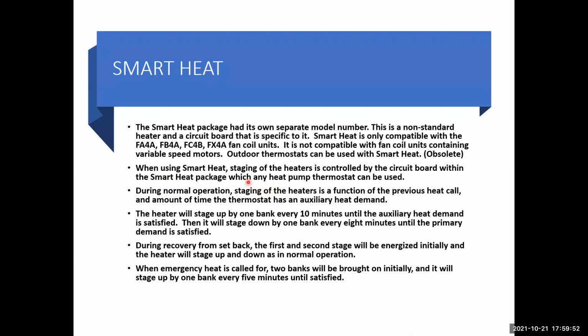When using the smart heaters, staging of the heaters is controlled by the circuit board within the smart heater package, with which any heat pump thermostat can be used. During normal operation, staging of the heater is a function of the previous heat call and the amount of time the thermostat has an auxiliary heat demand. The heater will stage up one bank every 10 minutes until the auxiliary heat demand is satisfied. Then it will stage down one bank every 8 minutes until the primary demand is satisfied.